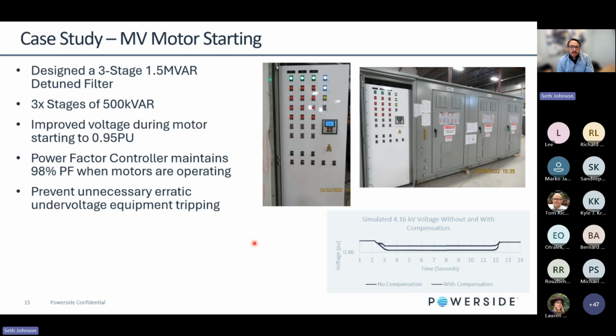So this system is designed to operate 2 ways. It goes into a motor starting sequence where it provides VAR compensation and brings in the stages needed to do the motor starting. And then it will switch over into a power factor control mode. And that's what we have here, a power factor control right here. Once the motors are up and running, we're engaging stages of VARs just to maintain power factor, which also helps improve voltage.